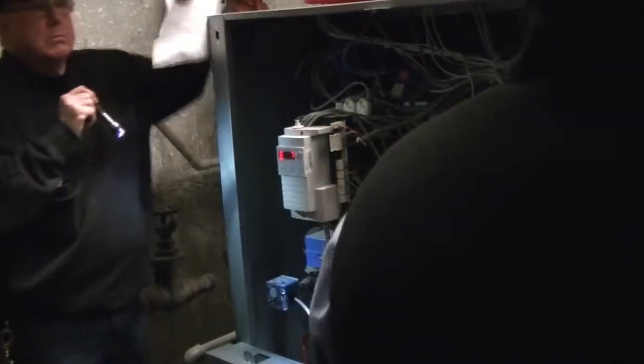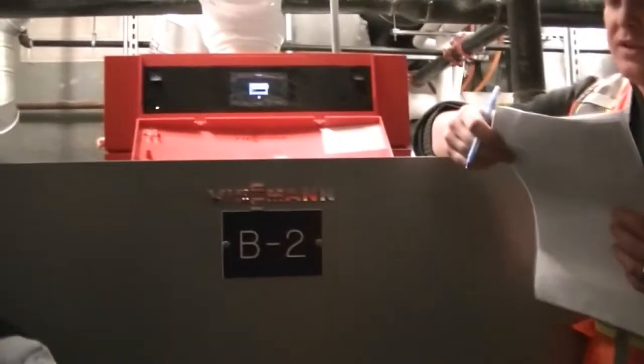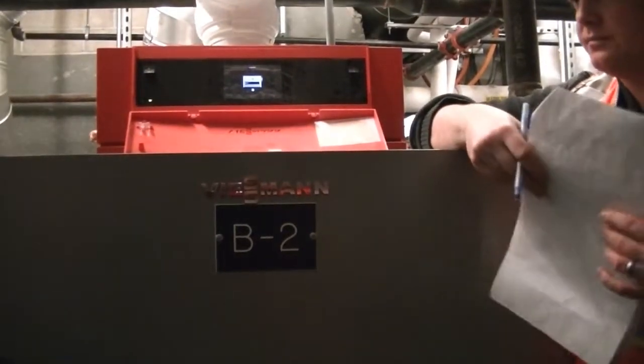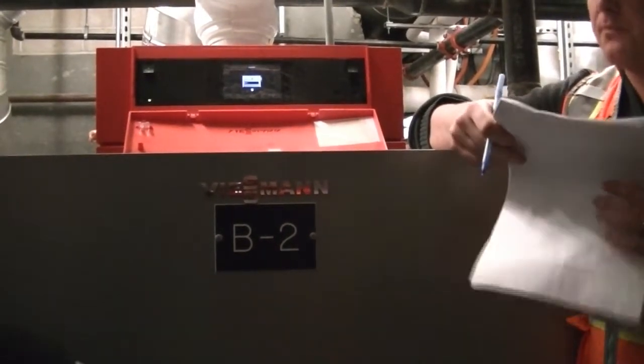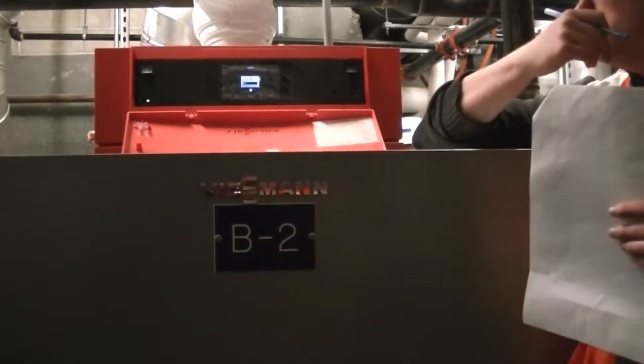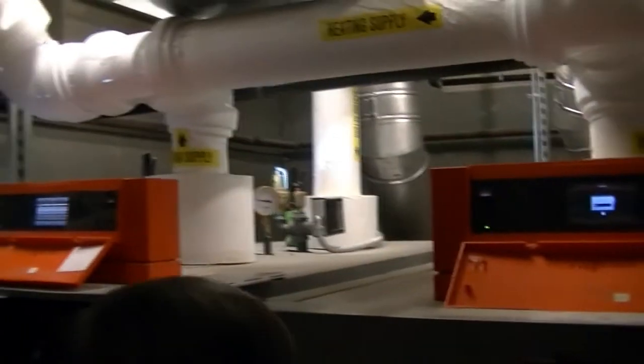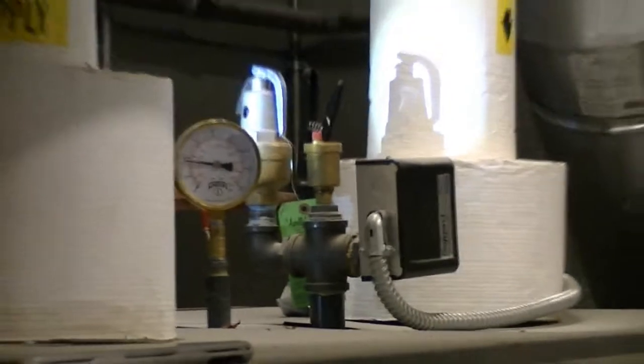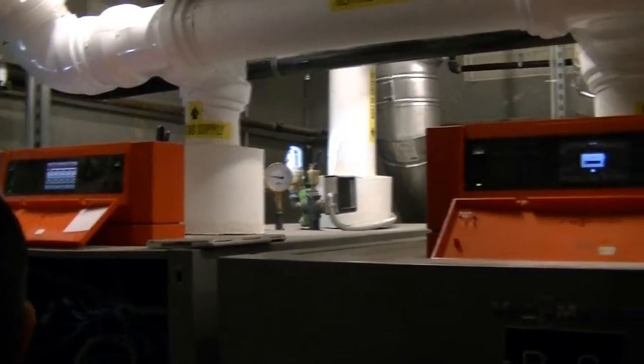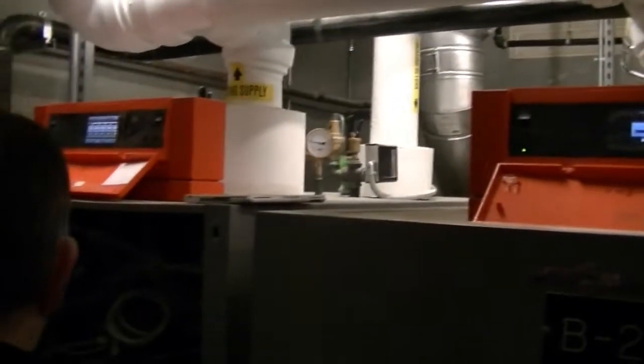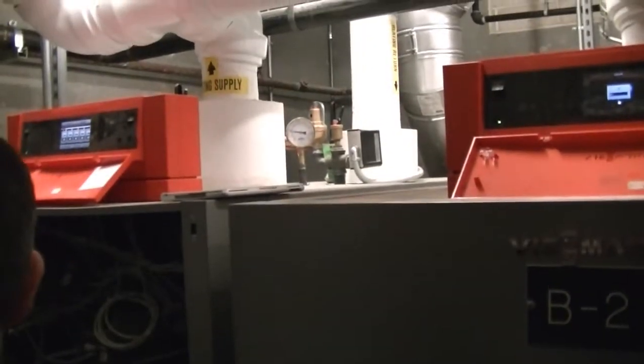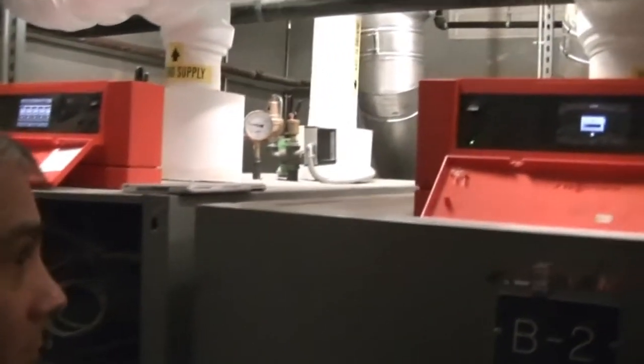Do you mind if I go through some of the maintenance items from the O&M manual? Test the pressure relief valve and check the proper operation. Yep. So how do you test the pressure relief valve, Kevin? You open it, right? The pressure relief valve is on top of the header, right near the low water cutoff on each of the boilers. And the only way to test it is to open it, make sure it relieves, and let it close again. But when you open it, we can't get it to shut down. So we don't do it. So that's something we don't do, Joe. So we shouldn't be doing that?